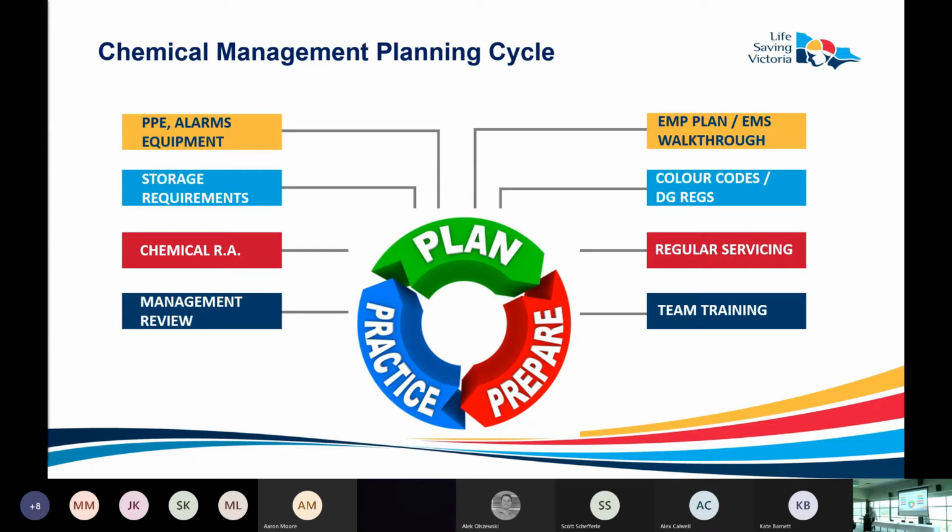So for us at Aquapulse, what that meant was getting an understanding of if the air handling system goes off in certain circumstances when the slide's running, you can have chloramine build up within the slide tower. And so we needed to know immediately if the air handling system switched off. So we were introducing new systems through our building management system to understand that.